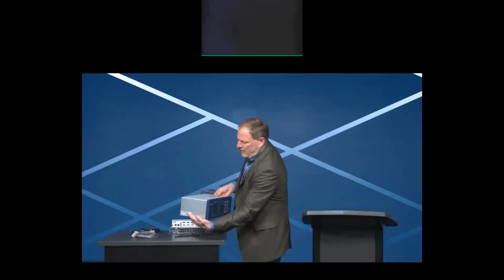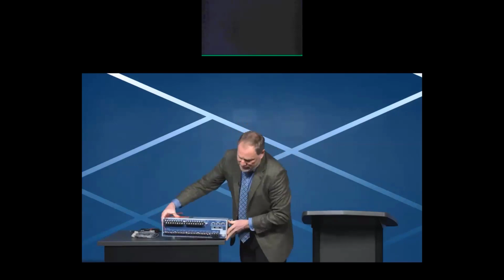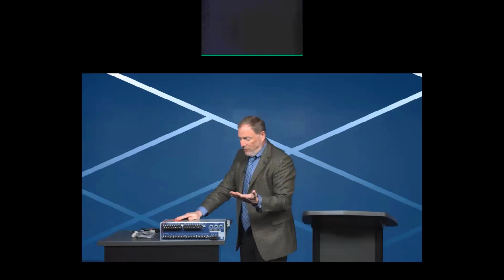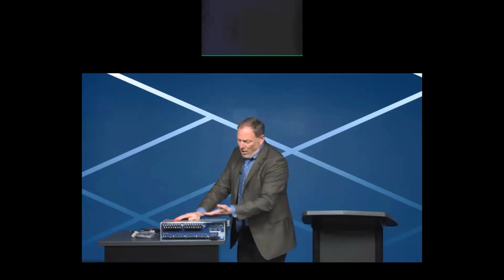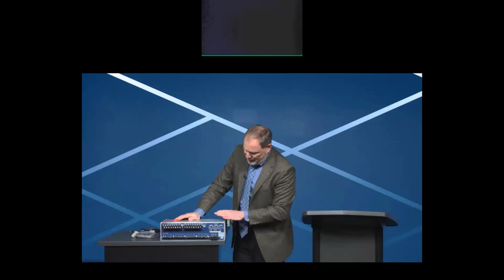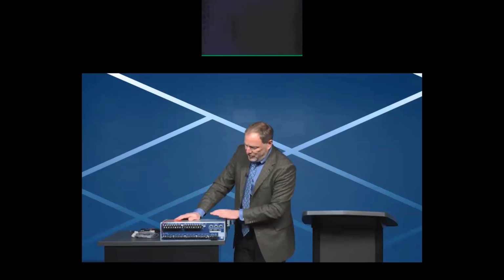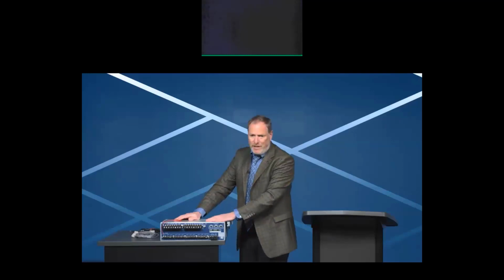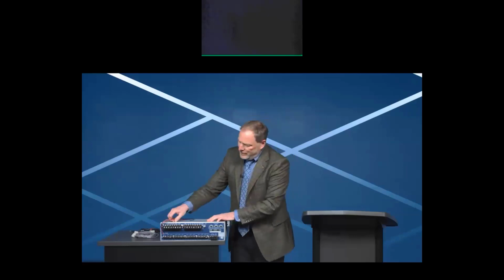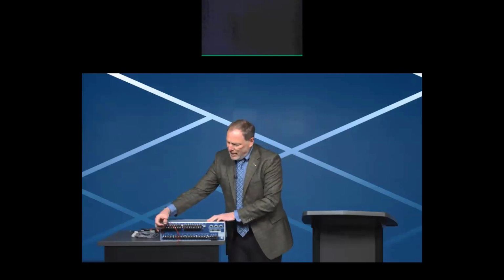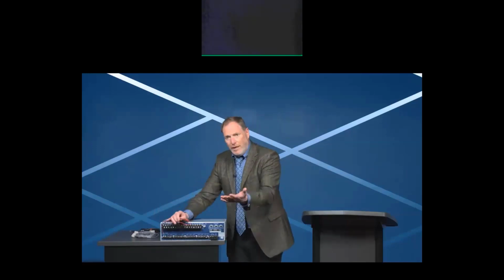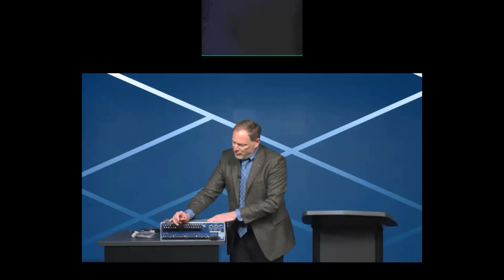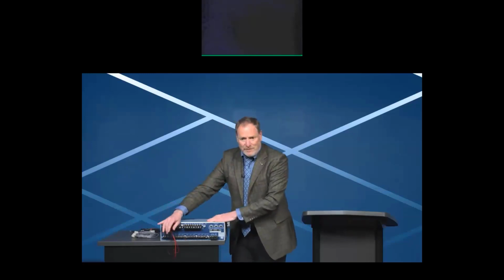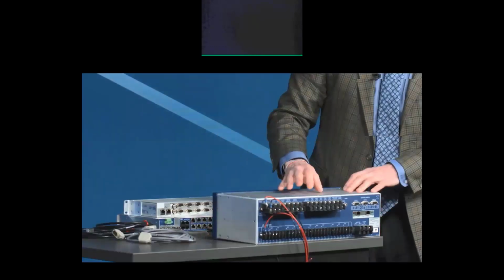In fact, here I have a relay that's truly a specialized computer designed to work 24/7 for up to 30 years and do its job. Considering all the components inside this box, we have in-service data showing that we have nearly an 800-year MTBF for the entire device. And we traditionally connect to the process using copper cables that travel thousands of yards from the relay cabinet to the process devices, the breakers and transformers in the physical process level.